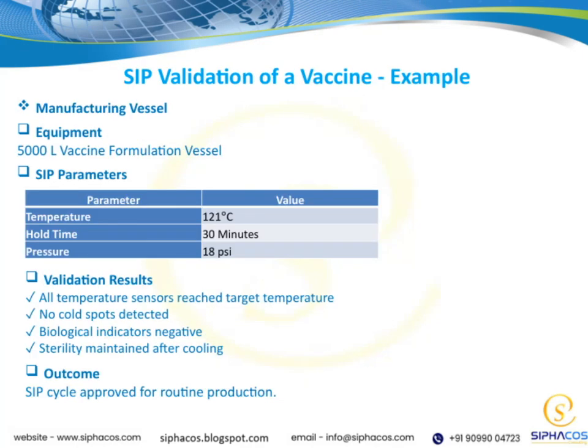Let's look at the validation results for the SIP cycle in our vaccine manufacturing vessel. Every temperature sensor hit the target. No cold spots were found. Biological indicators came back negative, confirming sterility was maintained even after cooling. With these results, the SIP cycle is approved for routine production. The key parameters were 121 degrees Celsius, held for 30 minutes, at 18 psi pressure, all in a 5,000-liter formulation vessel. This gives us confidence in the process's reliability and safety.